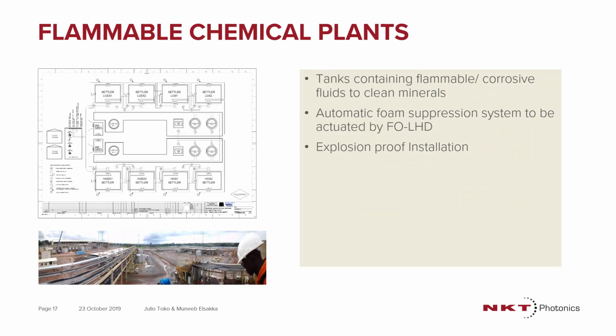The second aspect, when we talk about petrochemical plants, is that it's similar to mining. There are a lot of areas where you can use flammable fluids. Here's an example where you can have a lot of settlers when you're cleaning minerals, and those settlers have a lot of flammable fluid. As a matter of fact, it becomes very important to know exactly where this heat is coming from, where the fire has started, and to be able to flood the area of interest as precisely as possible. As we mentioned, with fiber optic you have a precision of about 10 to 12 inches. So the ability to pinpoint exactly where the fire is becomes very interesting for these different applications.